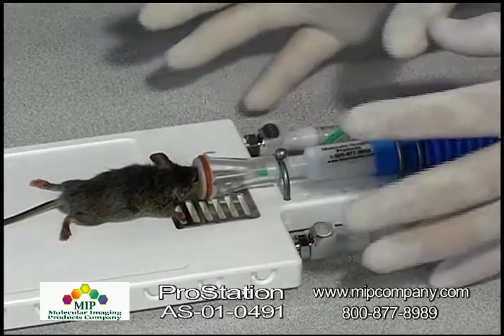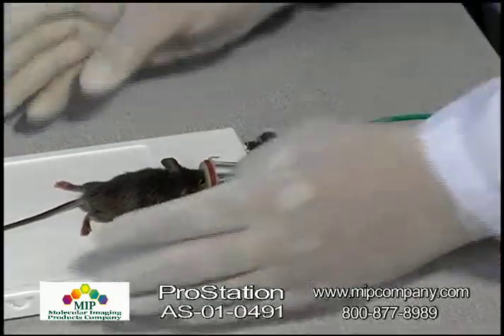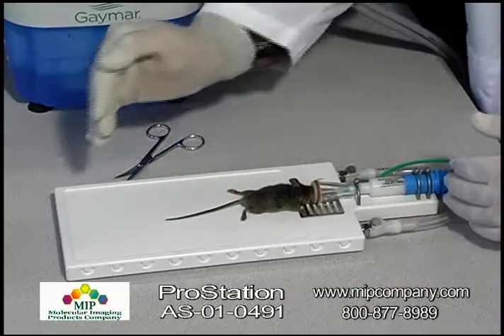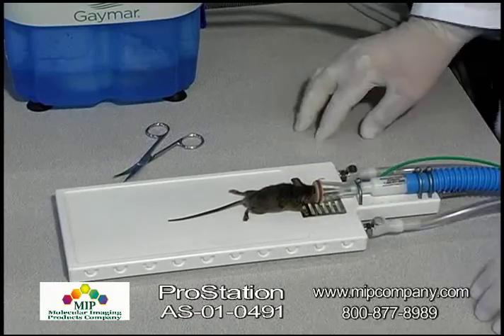So this entire system affords heat therapy via a hot water circulating pump. It is cold sterilizable, impervious to sharp objects, and gas sterilizable. The size of this platform is 5 inches wide by 13 inches long, and it will accommodate mice, rats, and other small species.